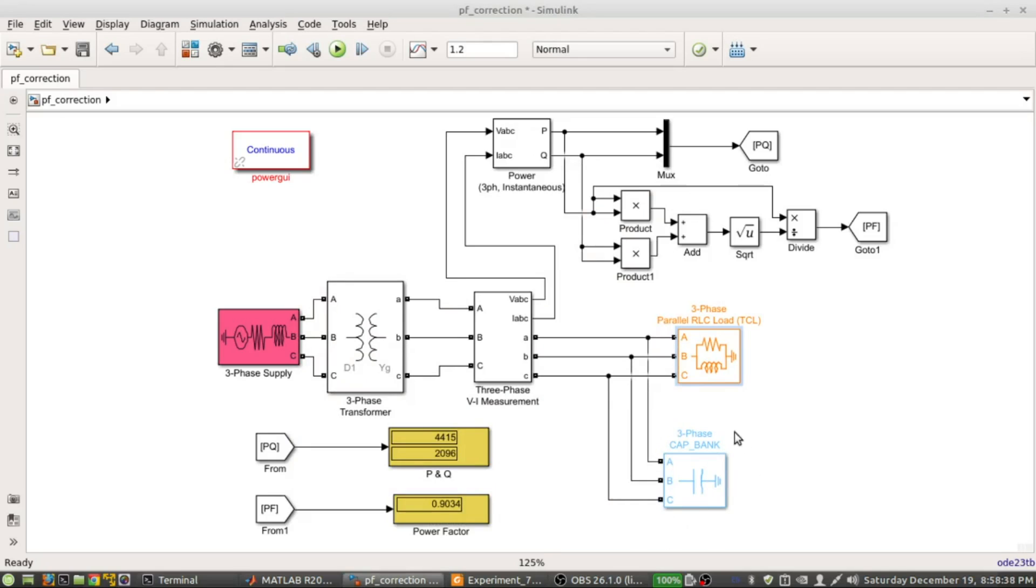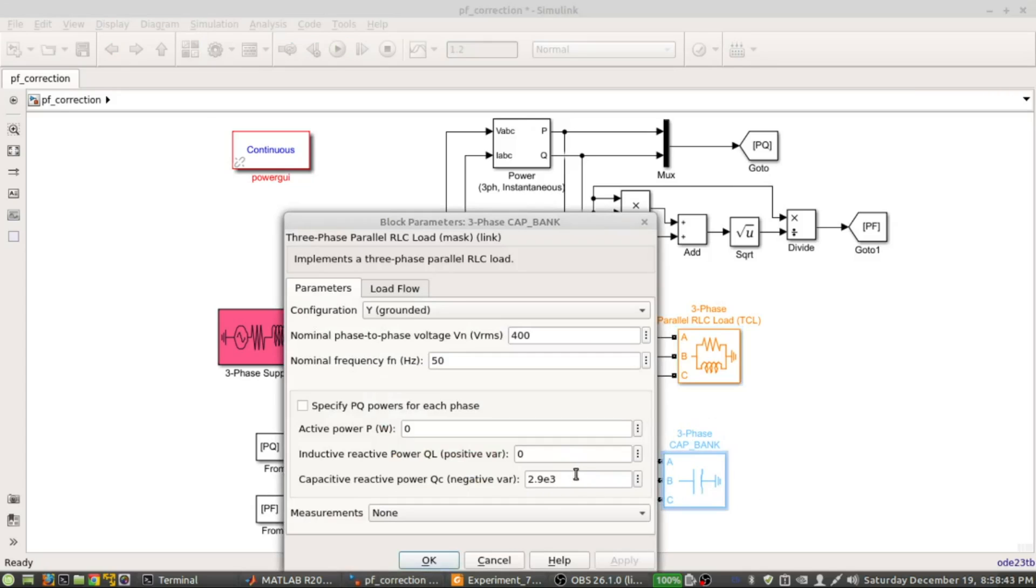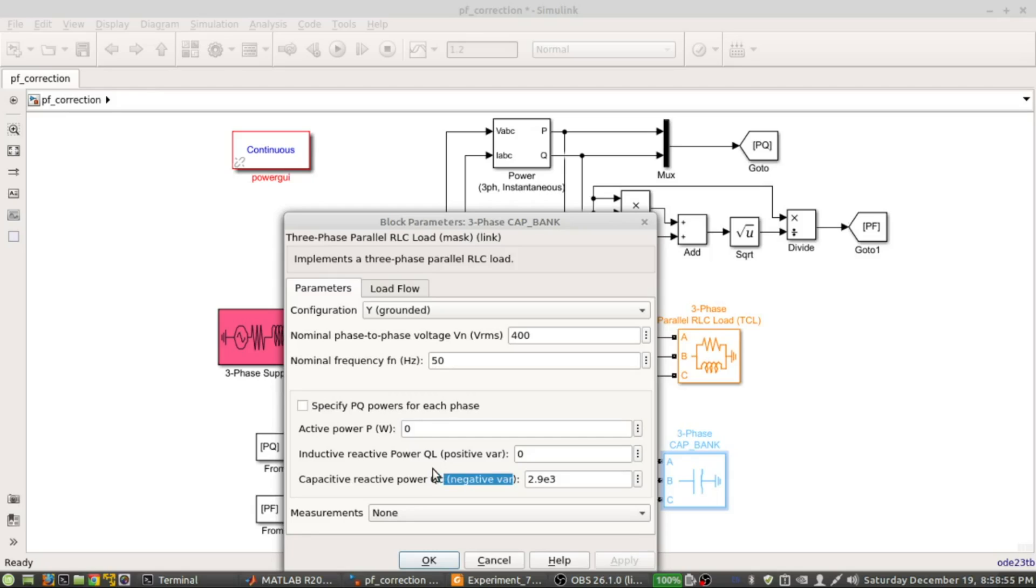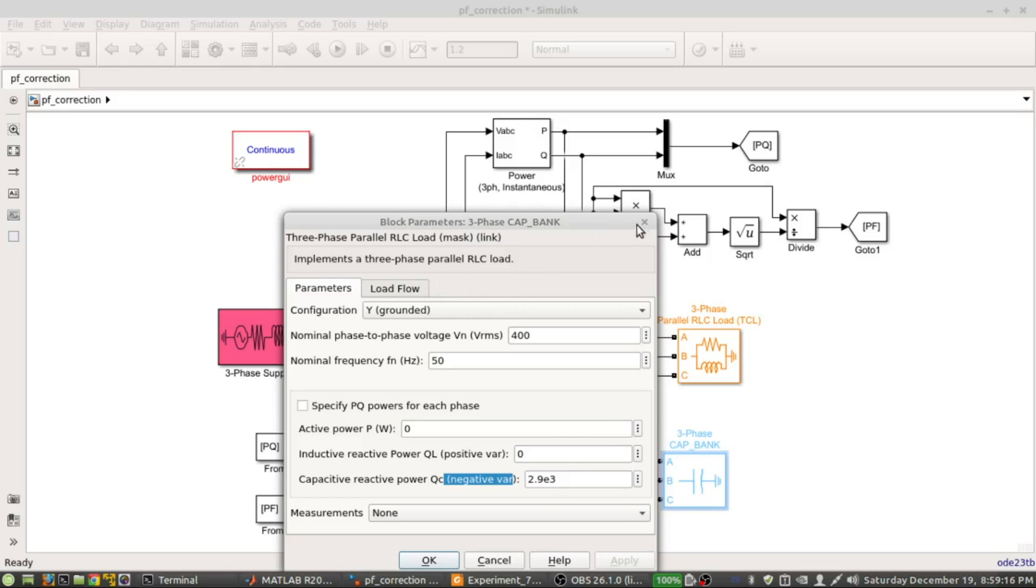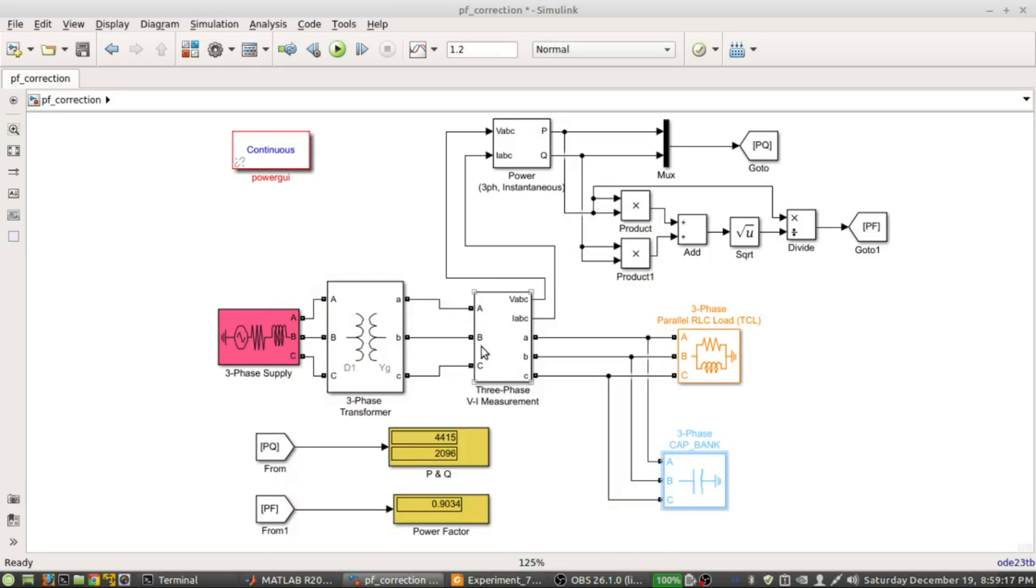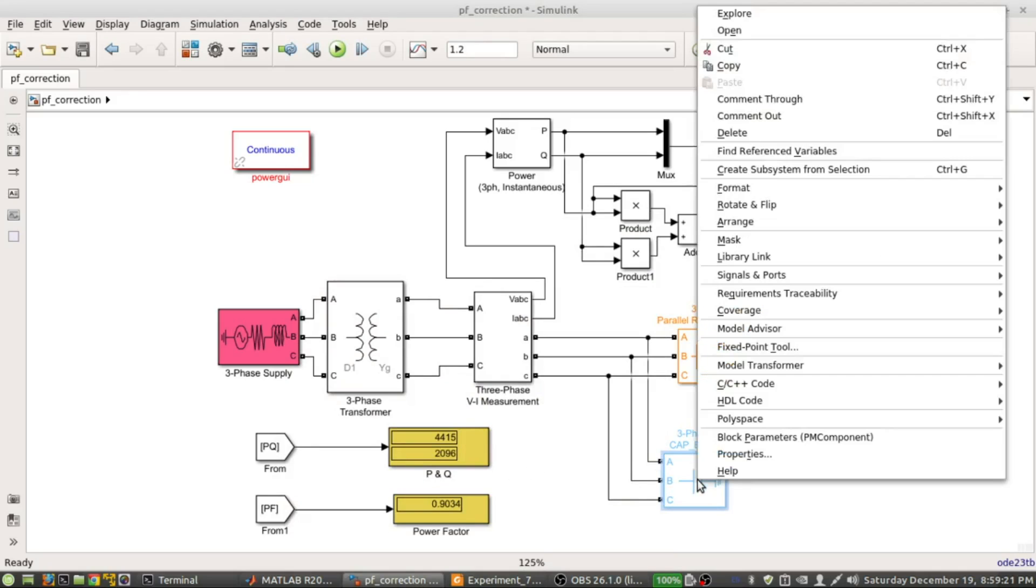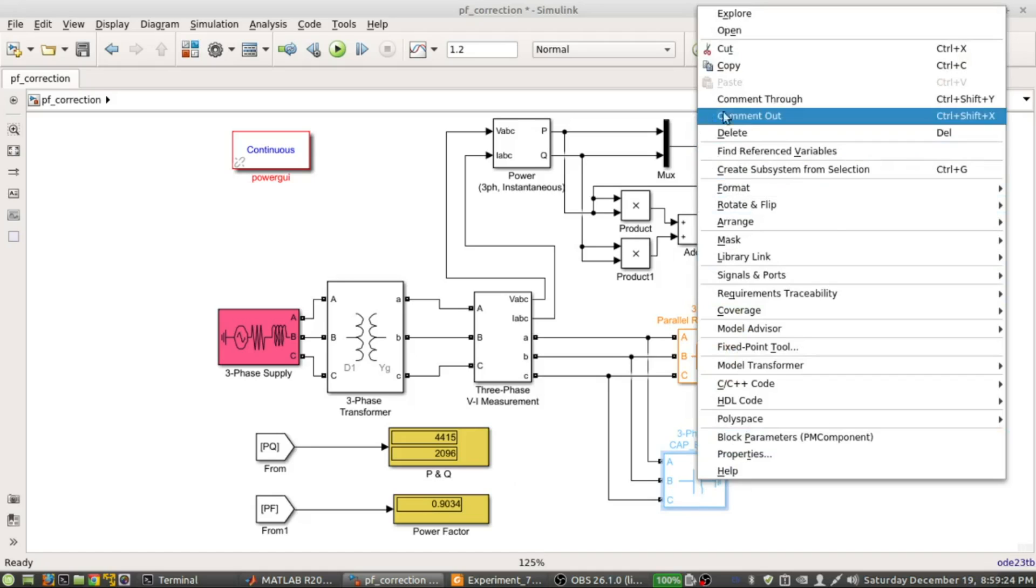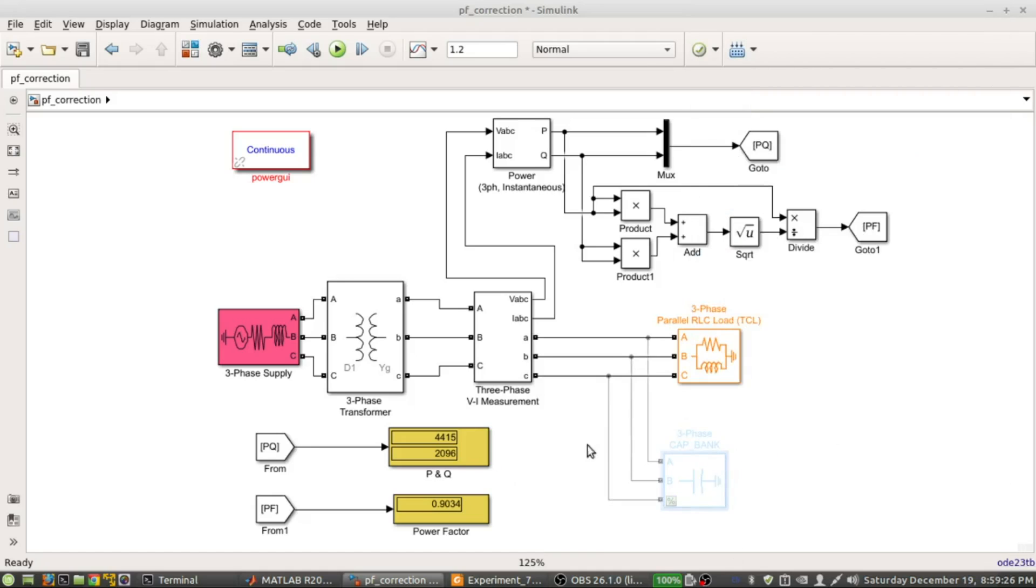Here this is the main capacitance bank. We have supplied 2.9 times 10 to the power 3, that means 2.9 kilovar negative. In previous calculations I probably showed that we need around 2800 and something var negative, so here 2.9 is given. If we apply that 2.9 kilovar negative, then the power factor should be around 0.9 because we have found it in our calculations. Let's first focus if there is no capacitance bank - that means if I comment out this one, this is not available. This is a typical system where no power factor improvement has been done.